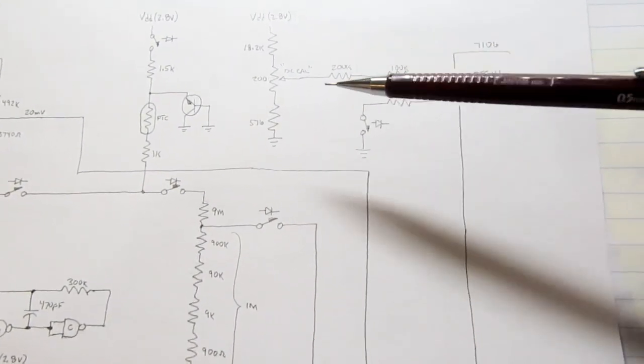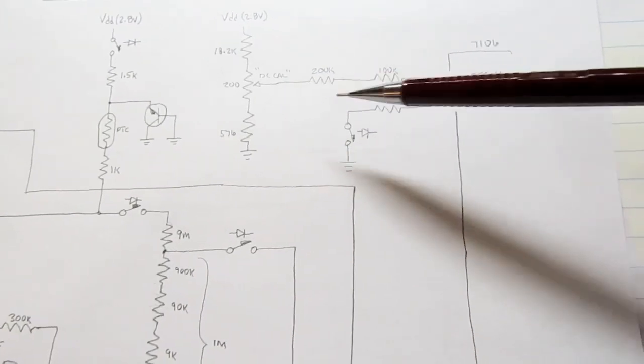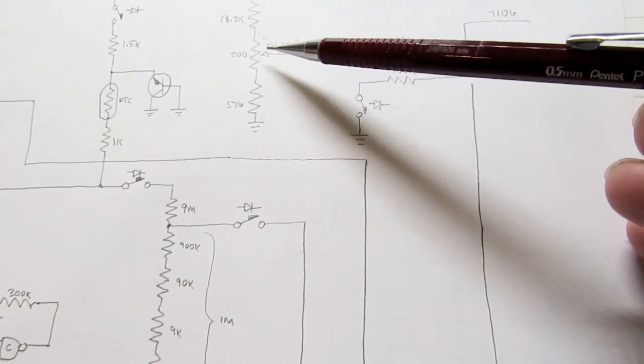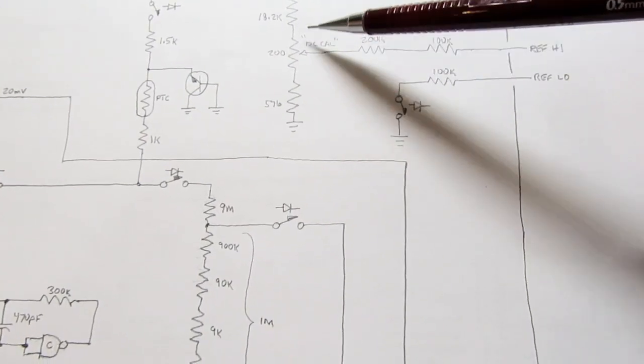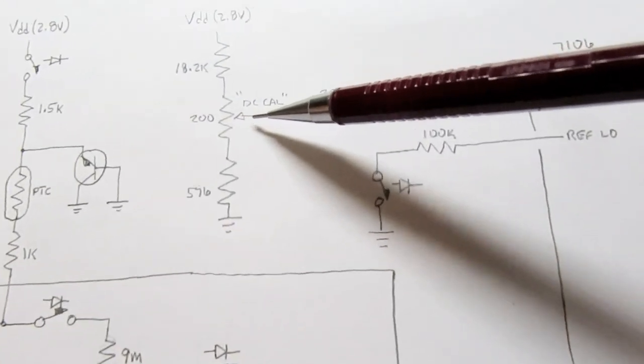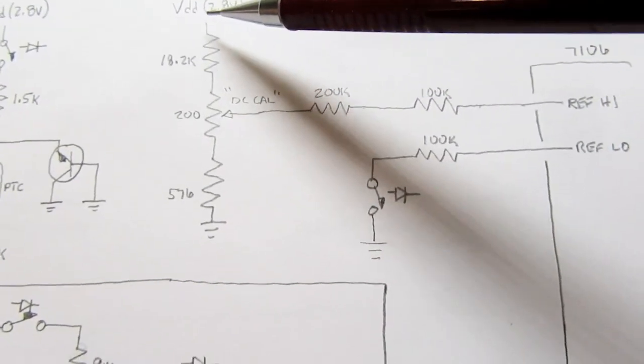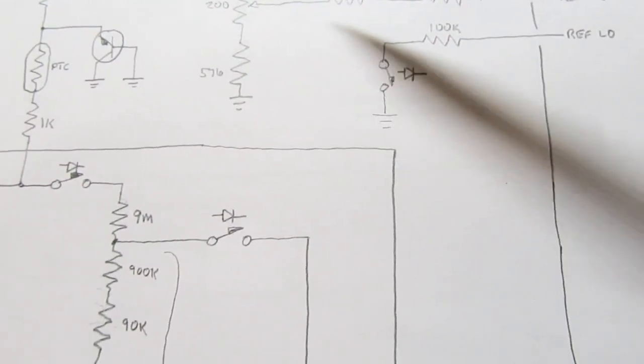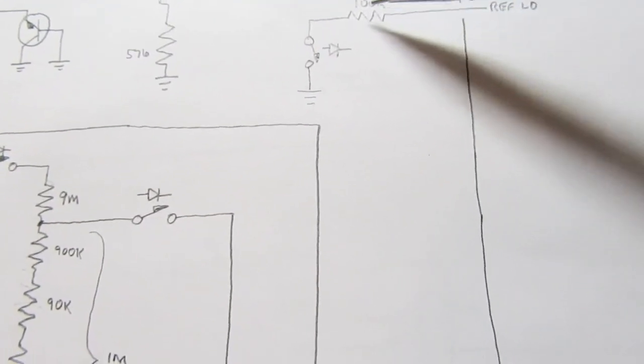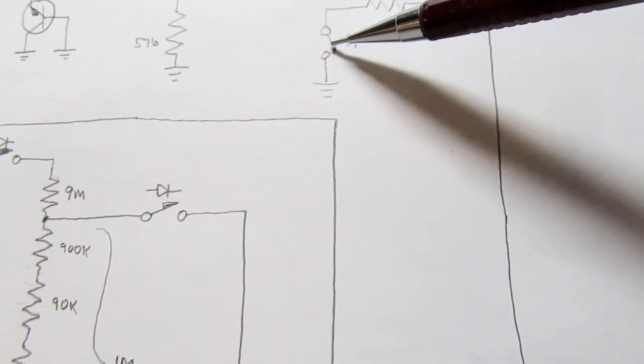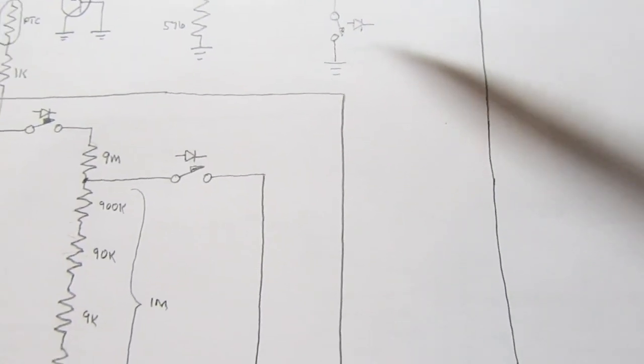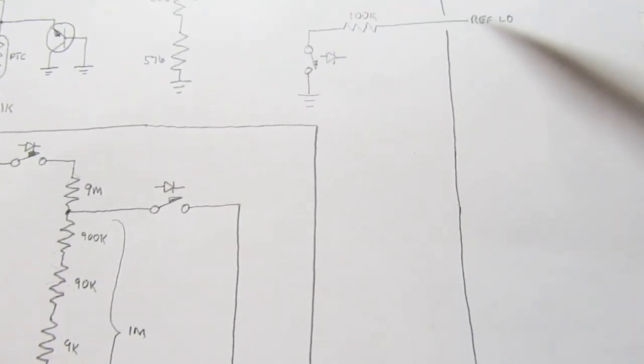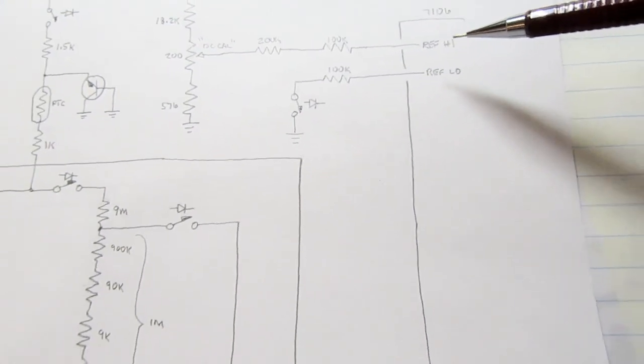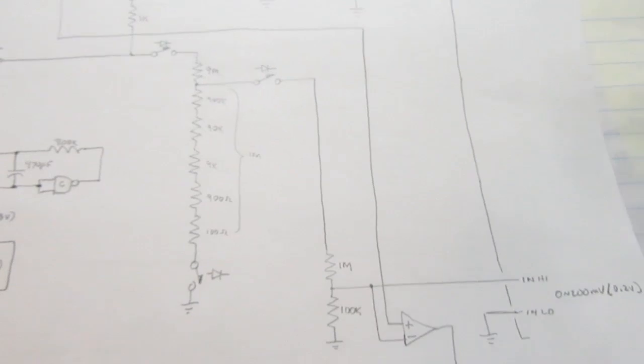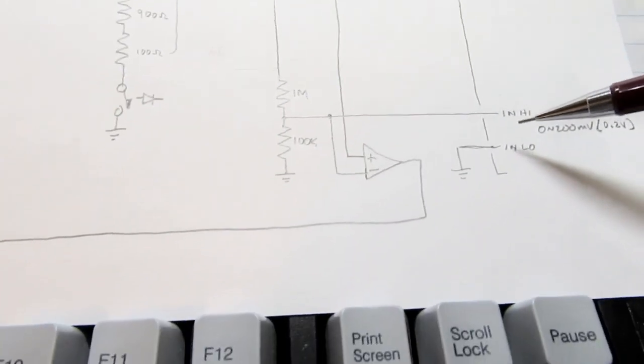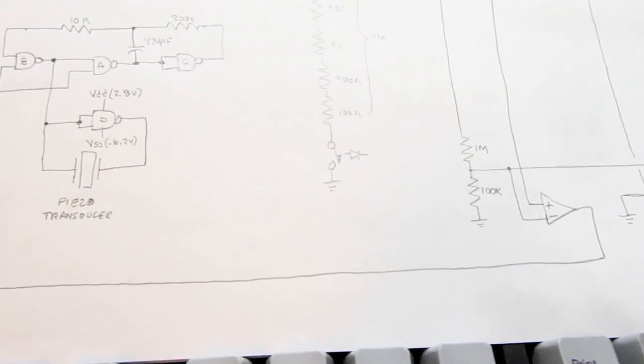It's used more like it is in its voltage measuring mode, where the reference inputs are just tied to a voltage, a DC calibrated voltage derived from the VDD and these resistors, and then applied to the reference input, and the reference low goes through a switch back to circuit common. So the reference voltage is sitting here at 0.1 volts all the time. So all we're really changing now is the input voltage. So let's see how that's derived.